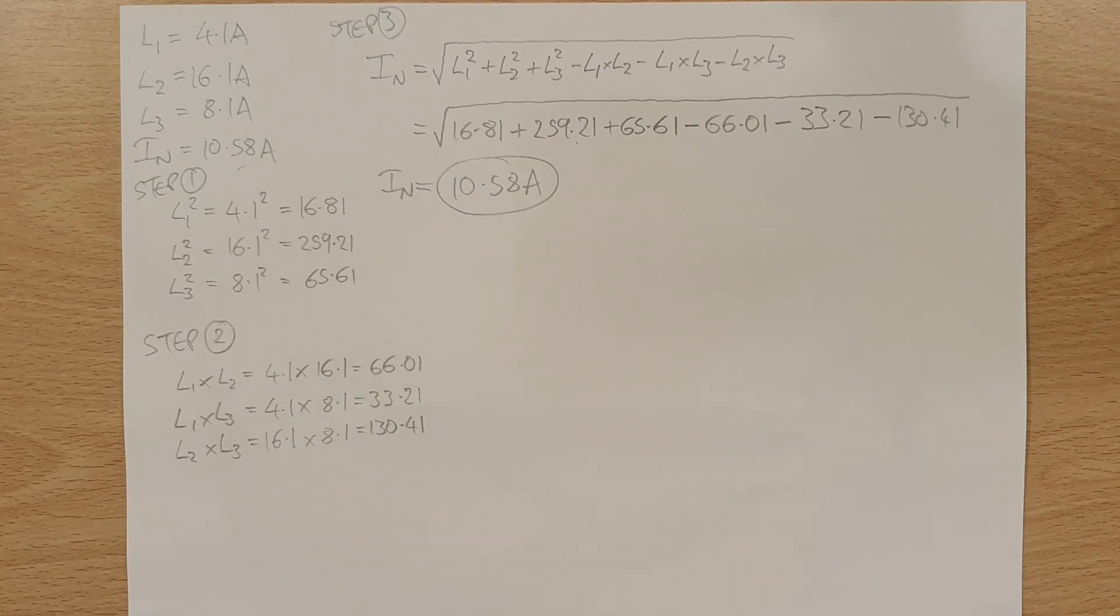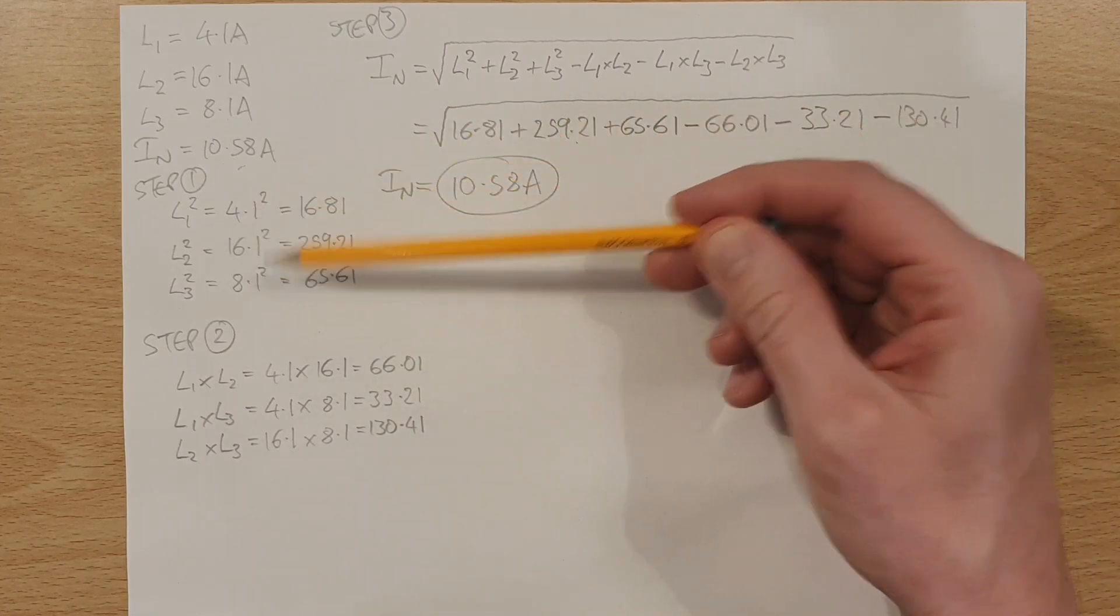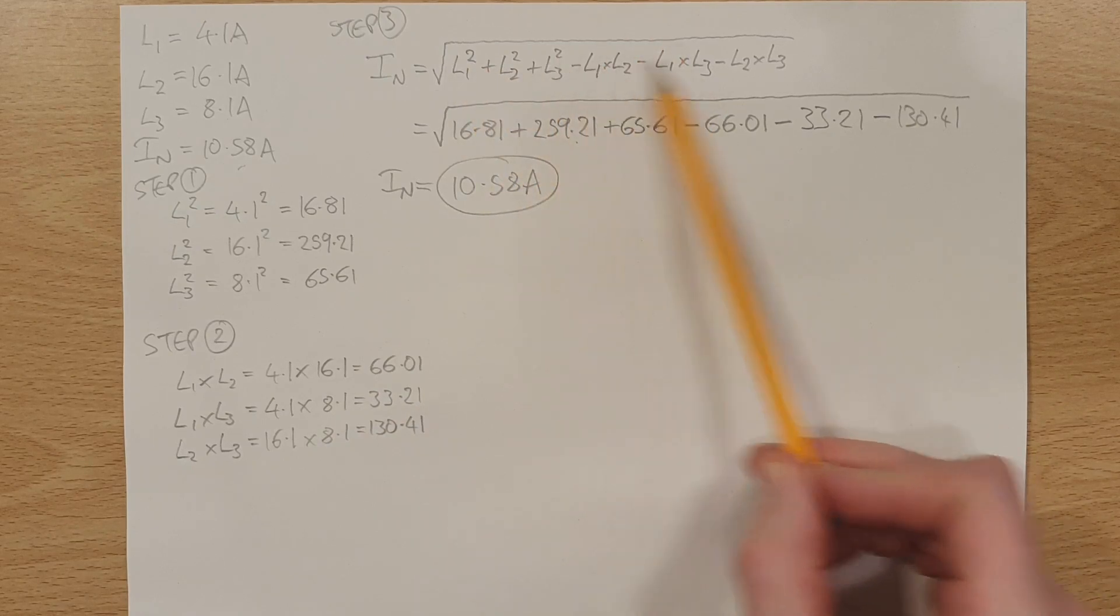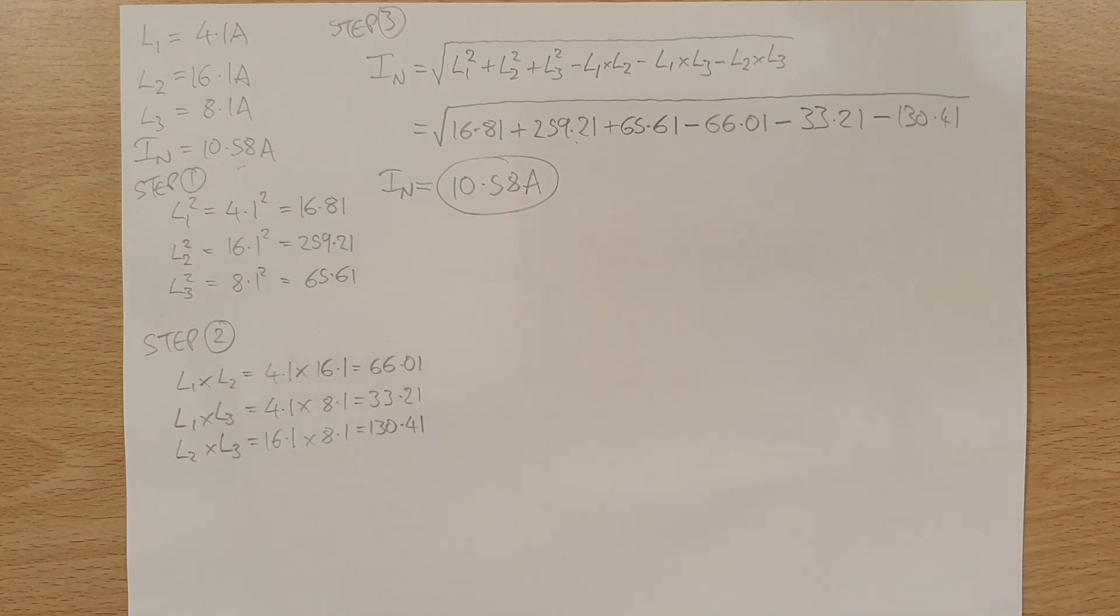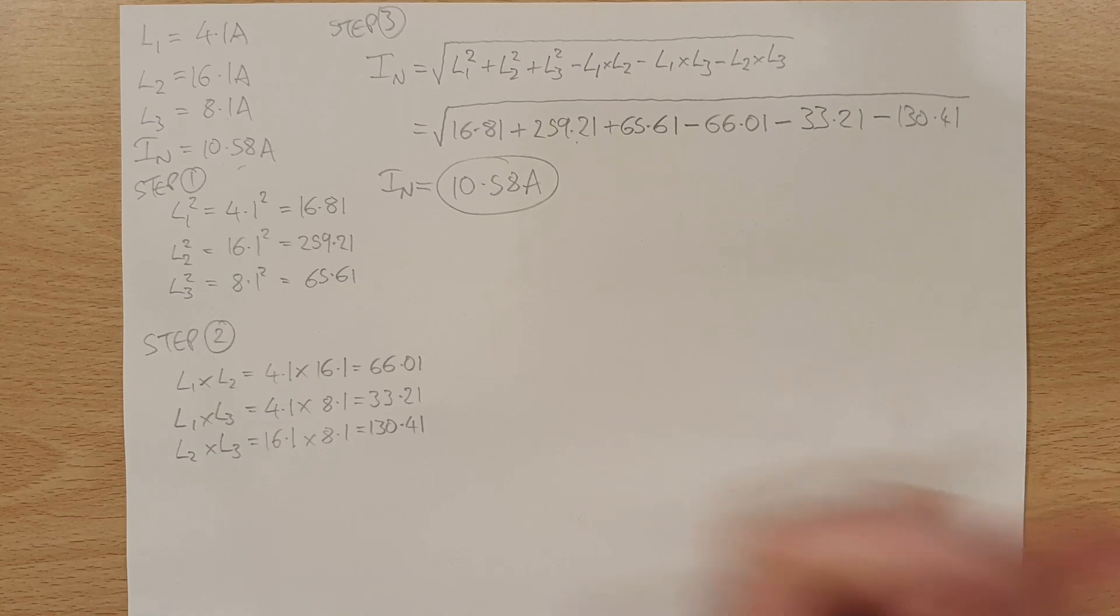So again, quite a good method. I don't think it's overly complicated. The first time you see this formula, it looks a little bit intimidating, but if you break it into stages, square the currents, and then in step two, multiply each current by each other current, and then we add the squares together, and then we take away all of the multiplied numbers and square root the whole thing, we end up with the neutral current. A slightly easier method, I think, and an accurate method, absolutely. So if this is your preferred method, then feel free to use it following the cautions that were mentioned earlier on in this video. So at this point, all that's left to say is thank you very much for watching.